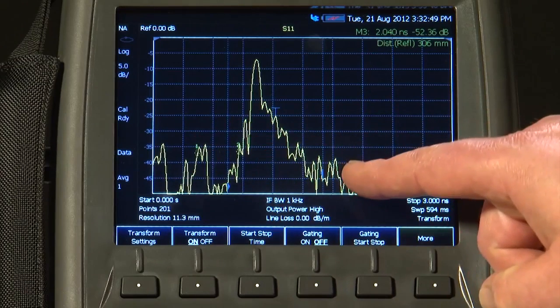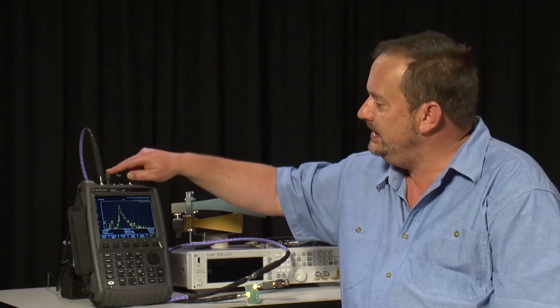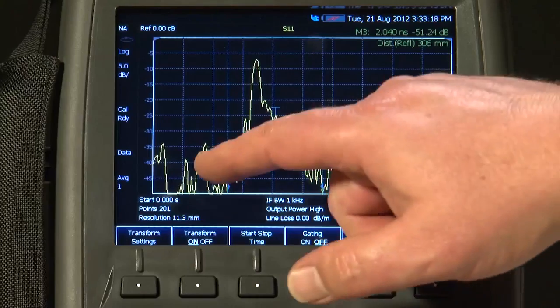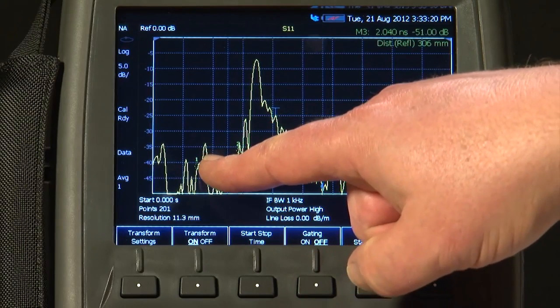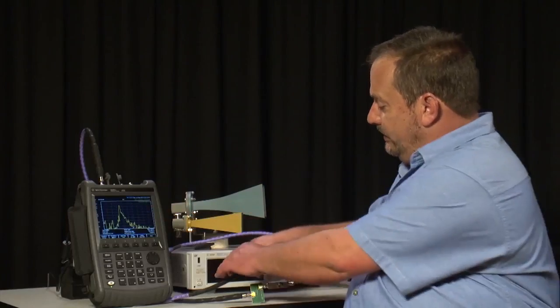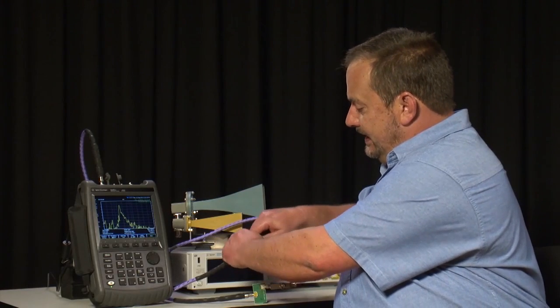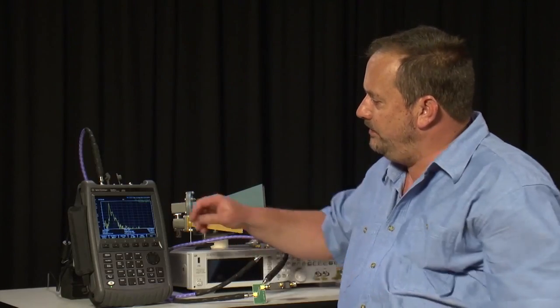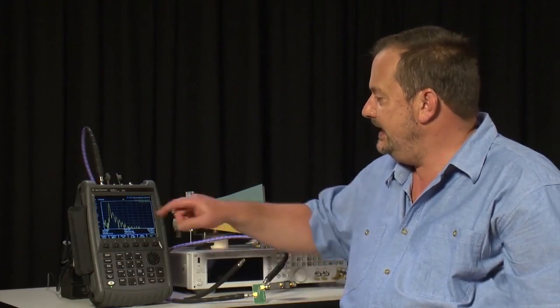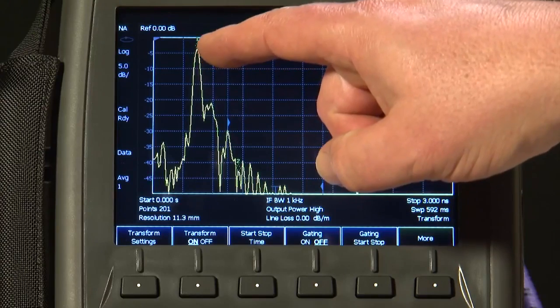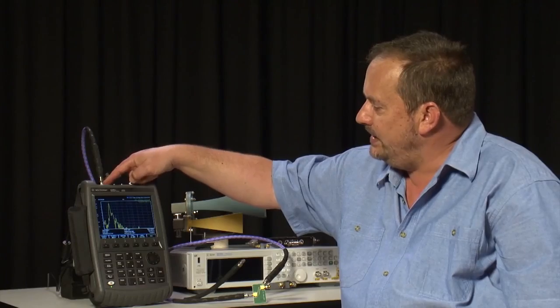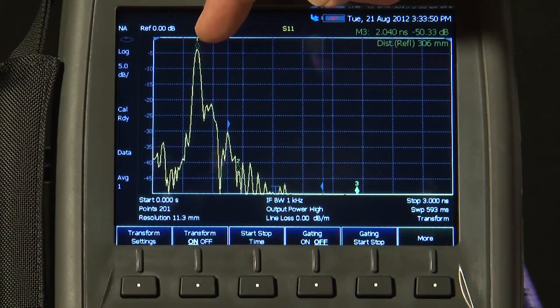Now if you're wondering what all these other bumps are on the trace, I can quickly show you this one here I know will be from the connector join here at port 1 on the analyzer. And this one here, which I've marked with marker 1, is going to be this join here, which I can quickly show you by separating the cables. That has created an open circuit on the end of this cable and you can see marker 1 is on that peak. So we know that that distance from the reference plane, port 1, is the length of this first purple cable.